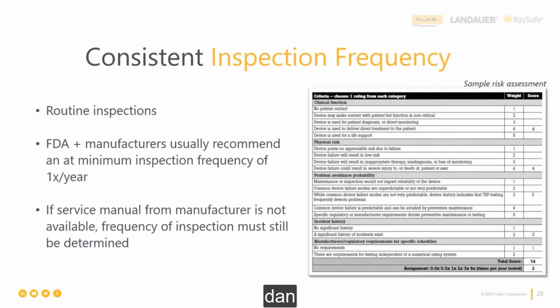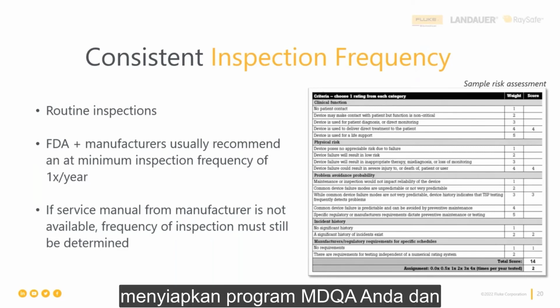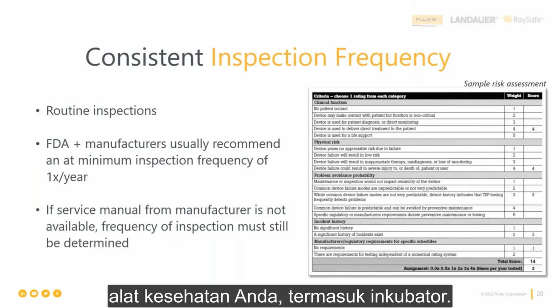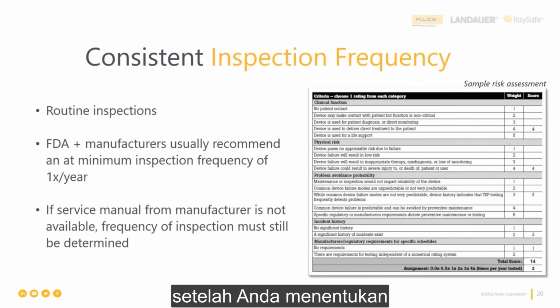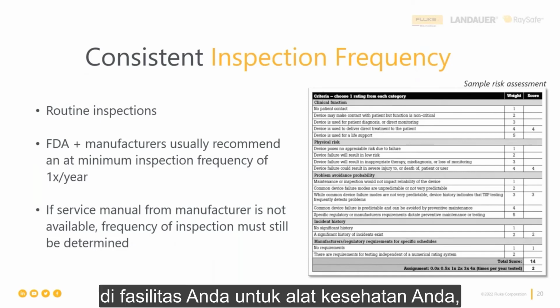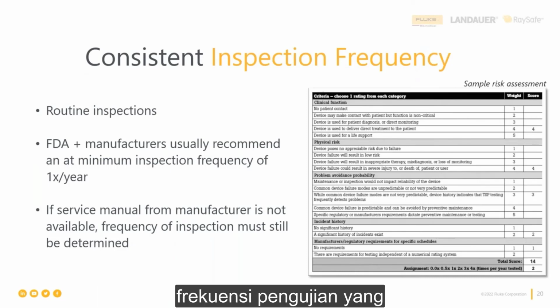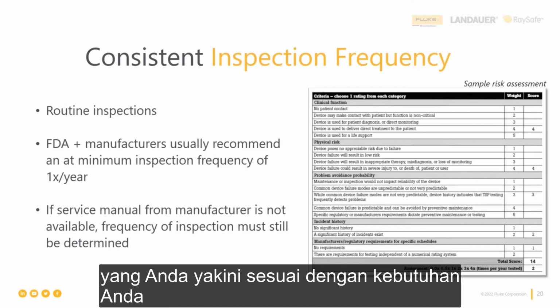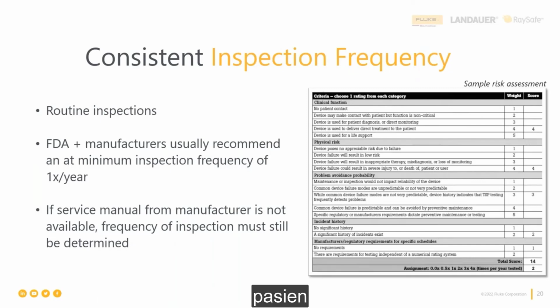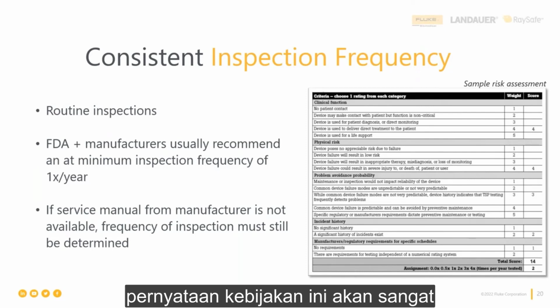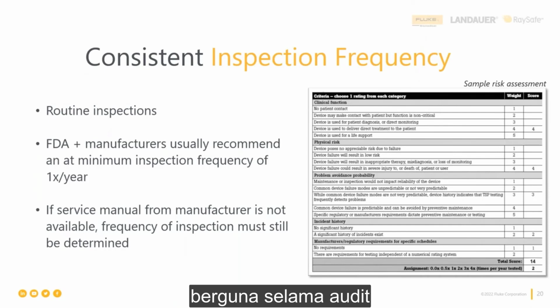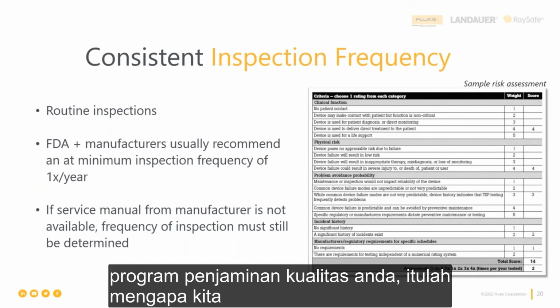You can go in and explore this particular part of setting up your MDQA program and complete this assessment for your medical devices, including the incubators. So once you determine the inspection frequency in your facility for your medical device, in this case an incubator, the testing frequency that you believe to be appropriate for your equipment, for your facility, for your patients, please be sure to have a written statement with the justification for that particular frequency documented. This statement of policy will come in handy during audits of your quality assurance program. That's why we recommend doing so.